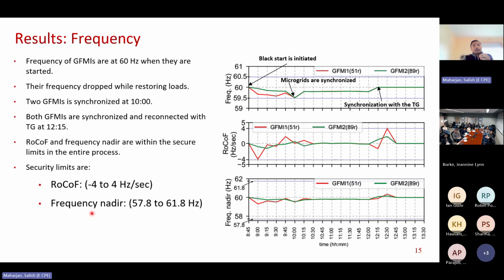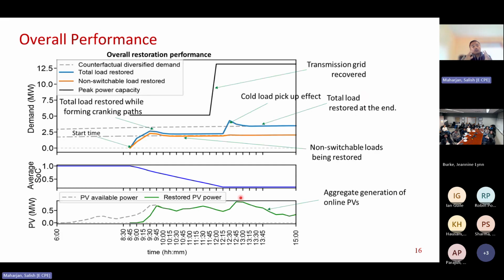So these are the results in terms of frequency. When the blackstart was initiated, both the grid forming inverters are operating at 60 hertz, and once they start picking up the loads, their frequency starts dropping as shown here. And at 10, basically, they synchronize, right? Their frequency got synchronized, and they continue at the same frequency all the way until 12, right? And when they finally get synchronized with the transmission grid, they follow the frequency of the transmission grid, which is 60 hertz. And the second figure shows you the RoCoF at different instances, and the frequency nadir in the third figure at different instances. And here RoCoF and frequency nadir are both under the security limits.